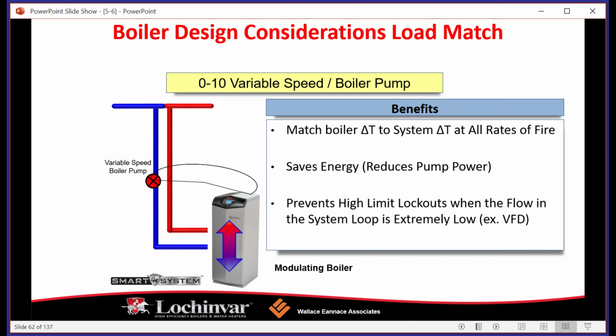It's going to slow down, the fan speed is going to slow down the burner, and it's going to say, I don't need necessarily 1 million BTUs. Let's go down to 700,000 BTUs. As we start to get closer to our set point, it's going to continue to ramp down and down and down. Again, which gives us that efficiency, right? So we may only need on a certain day 300,000 BTUs, which the boiler is going to ramp down. It's going to run at, basically, slow and low.